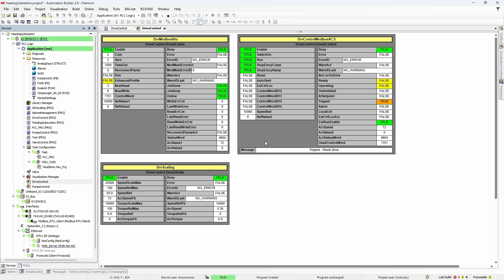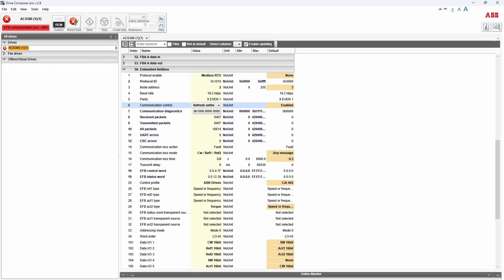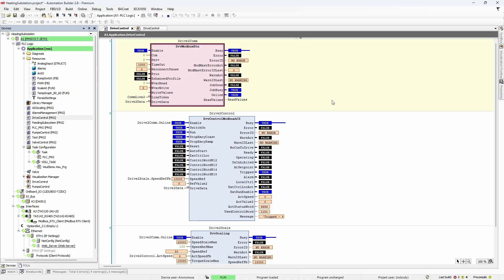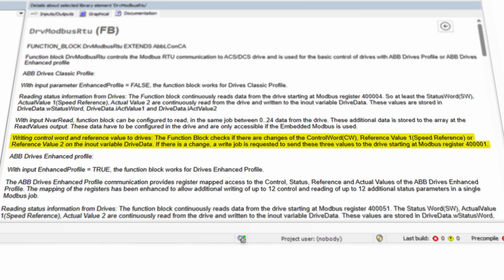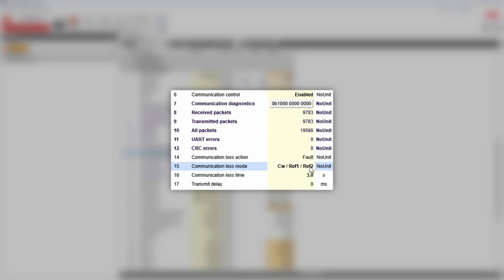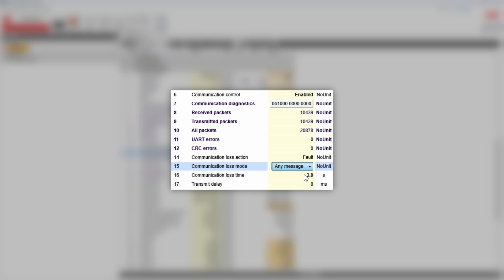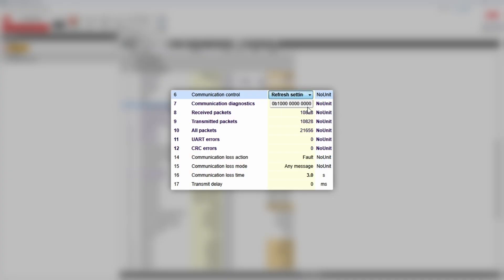Until it doesn't. Drive Composer says EFB communication loss — but the communication is there. The drive modbus rtu function block sends write requests only if there is a change in reference or control word; if those values haven't changed since the last request, the function block will only read status information. But parameter 5815 tells us that the drive will trip into a communication fault if there were no write requests to control word, reference1, or reference2 within a three-second interval. Since we can't control how the function block works, we change parameter 5815 to 'any message', which makes the drive trip only if there are no read or write requests within three seconds. Don't forget to refresh settings.